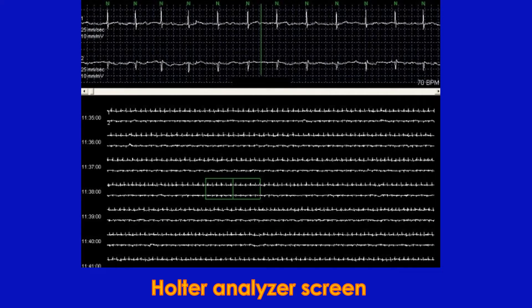A Holter analyzer is a computer with an appropriate software application to which Holter data is downloaded for analysis. Automatic printouts are available after the analysis. The medical technician who analyzes it can review representative ECGs for each abnormality and verify accuracy to avoid false reporting by the software. The supervising physician can also oversee the technician's report.